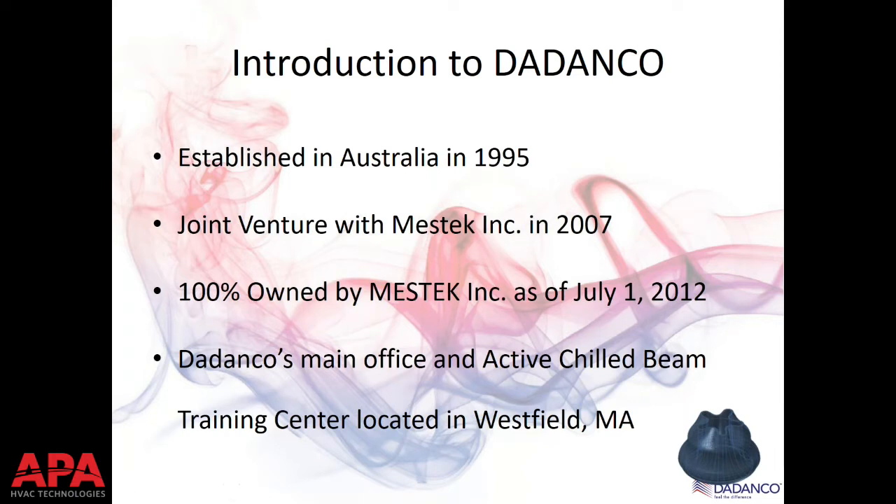We're using a constricted opening to force air through a nozzle — we'll dive into that deeper later. That's kind of how Dadanco got started, using perimeter induction systems along the perimeter of buildings in Australia and the U.S. Those systems have been installed 30, 40, 50 years ago inside government-style high-rise buildings and university dormitories. Chilled beams are really just taking that hydronic coil, traditionally at floor level behind an enclosure, and sticking it in the ceiling with nozzles and a sheet metal case.